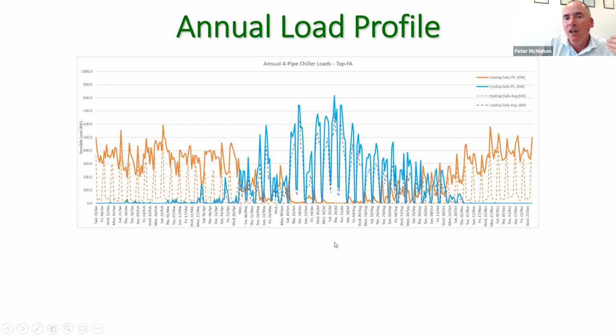So with this knowledge, we want to be, let's just say, a little bit more intelligent about how we go about selecting our equipment. So we try and select the multifunctional heat pumps to operate at maximum efficiency. We're going to get that maximum TER, and that's where we want the money. So we're a long way down the road from when we first used to start selecting these. Very often people used to oversize. There isn't really a great benefit in doing that. You're better off to buy two smaller units. You'll get a much greater efficiency.